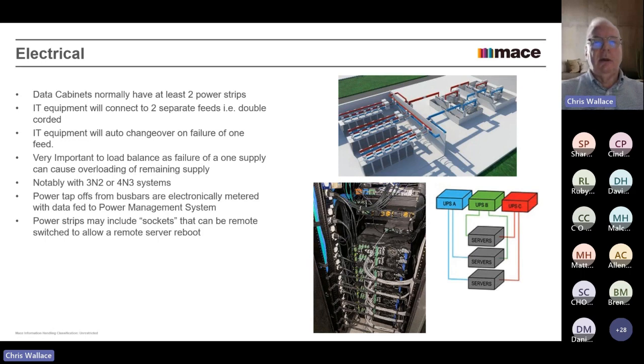They say a picture's worth a thousand words. So typically what we've got here is in the cabinet at the bottom. Typically you'll have a power strip on either side of the cabinet, and one will be red and one will be blue, as we said, from each of the blocks. And each of the server units or bits of IT equipment that the customer has is what they call dual corded. That means it has two cords and it will feed from red or from blue, or red and blue. It will sense the power all the time, and it will have a little STS, static transfer switch, in it. It will say, okay, blue's gone down, I'll just change to red. So basically, if you lose one supply completely, all the cabinets stay up, because they're all working with these little bits of equipment.